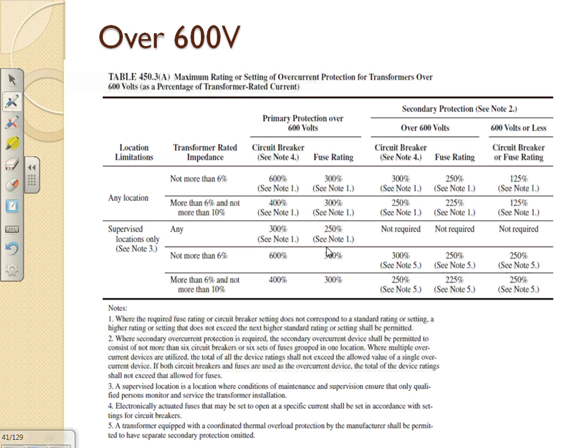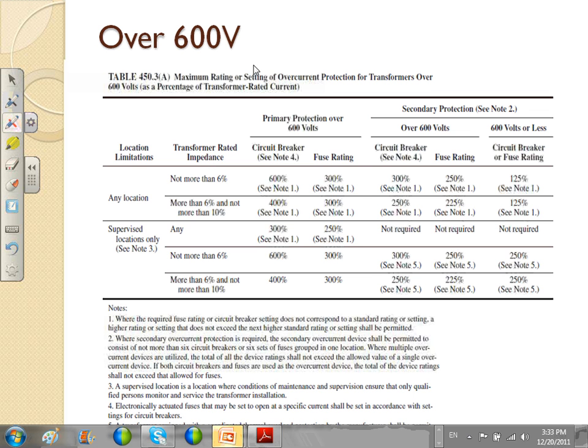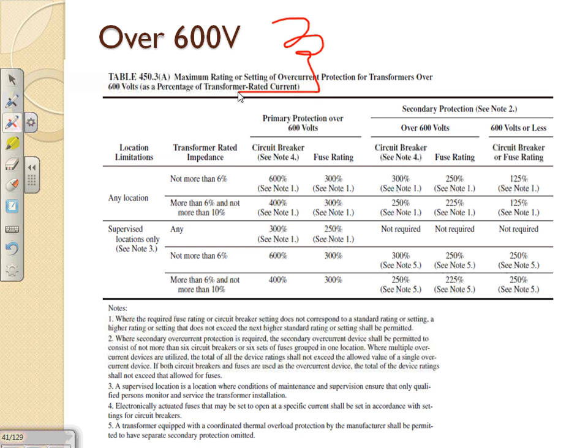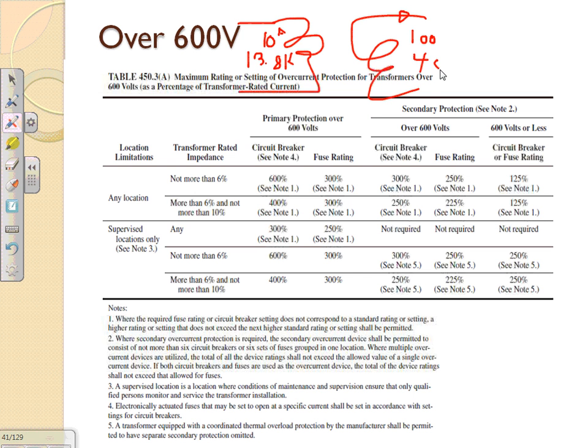Primary voltage. So take this. Here's my transformer, and I'm showing only one winding on the primary and one winding on the secondary. Let's say this transformer is 100 amp. I have 10 amp on this side, and I have 100 amp on this side. It's a step-down transformer. This side is 13.8 kV, and this side is 480, a 480 system. This is very simple, and I'm showing only one phase. You can imagine the three phases are going to be the same.